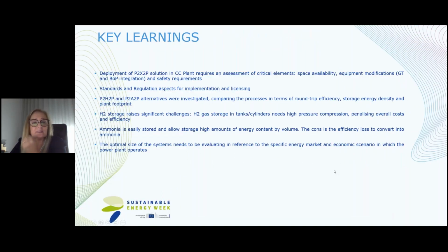So, next slide please. Here are the first lessons learned for implementation of these demonstrators. Deployment of these power-to-X-to-power solutions in combined cycle power plants requires an assessment of all elements critical for project development, such as space availability, BOP integration, and the ability of gas turbines to burn fuels with higher hydrogen or ammonia content. For higher percentages of hydrogen in the fuel, an upgrade of the gas turbines would be required, and of course there's the safety aspect.